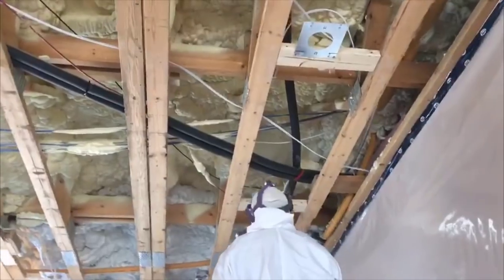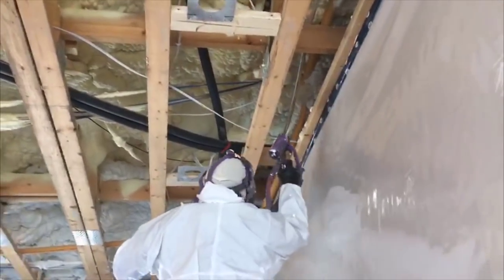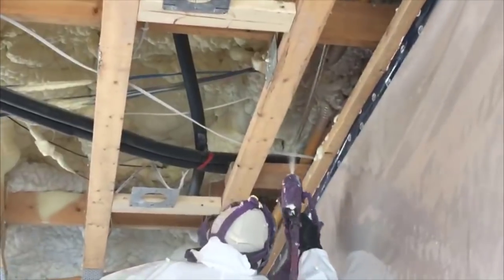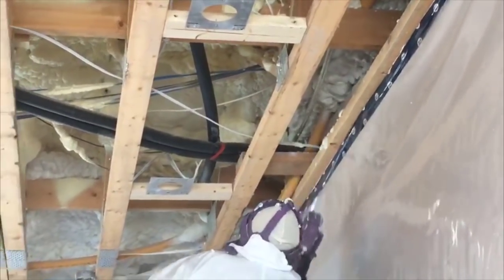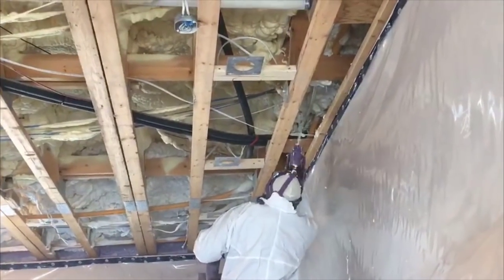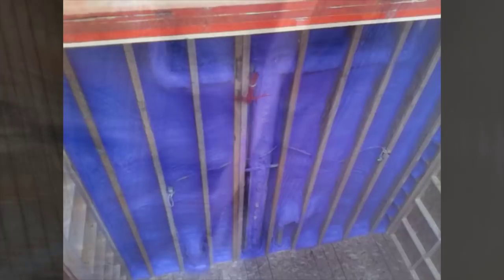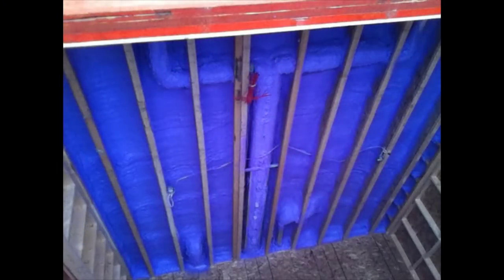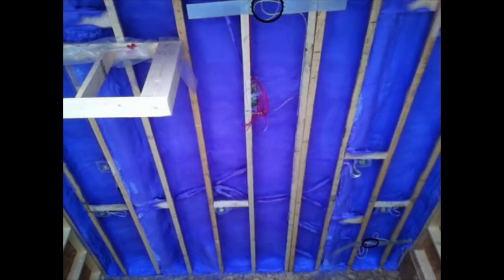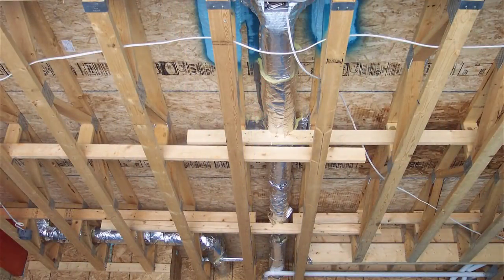From a practical standpoint for people building structures, if you have the approvals, or have a contractor in your area who has their product approved, then that is the absolute way to go, for a couple of reasons. It locks on to the galvanized tin of the ductwork very well. It seals it up. When you are insulating ductwork, you have to be careful to get the foam to wrap all the way around, 360 degrees, or construct it in such a way that if you can't get all the way around, you've closed it off. Because if you leave gaps and the ductwork is going to have cold air around it, then you're going to have an area where you can have condensation.